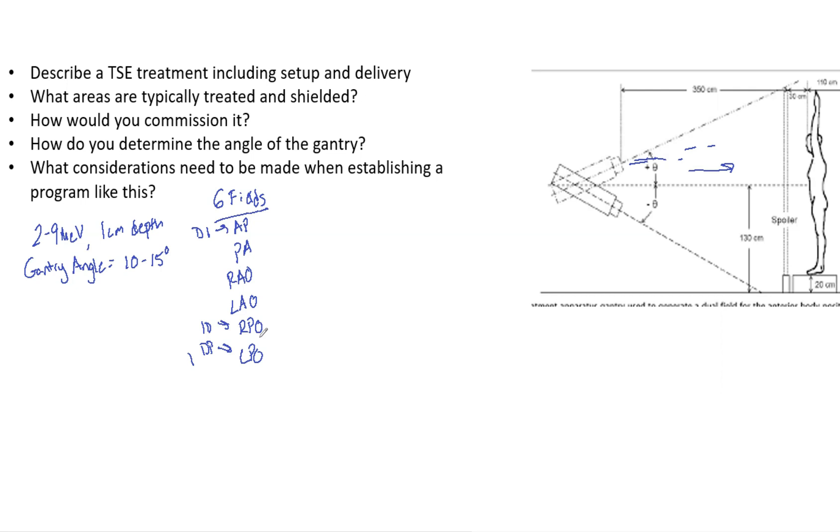The patient is at—what's actually mentioned here says 350 cm, but I'm used to somewhere around 400 centimeters, four meters. Again, that's dependent on your personal setup. You could also put what they call a beam spoiler: a 1 cm acrylic plate in front of the patient. Ideally, what we want is that 1 cm depth and 10% uniformity.